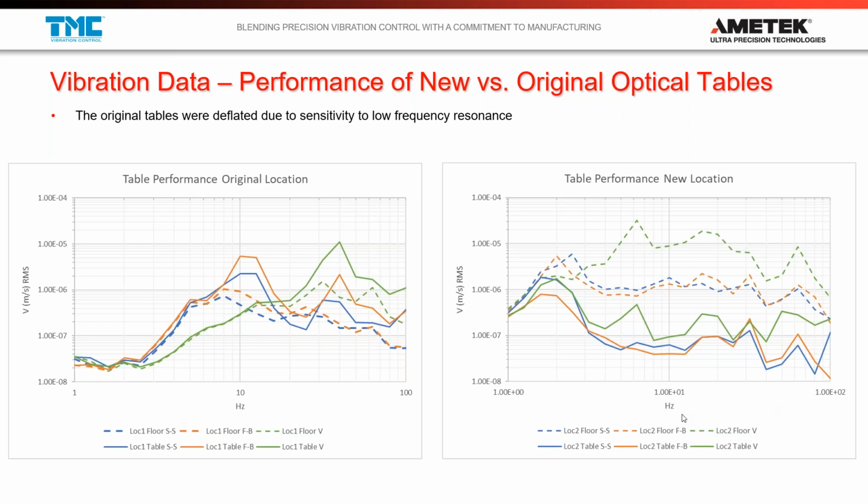And again, the takeaway is, we weren't necessarily able to replicate the exact floor conditions in the original lab. However, we were able to take out enough of the problem vibration that they were able to still perform their experiments and then benefit from the new humidity and the new temperature conditions in the new lab. So this was actually a pretty successful install.